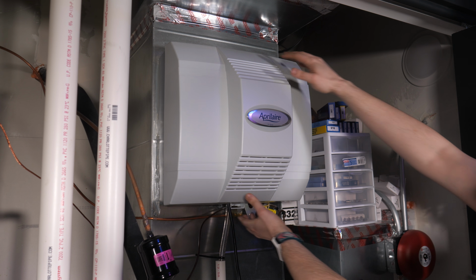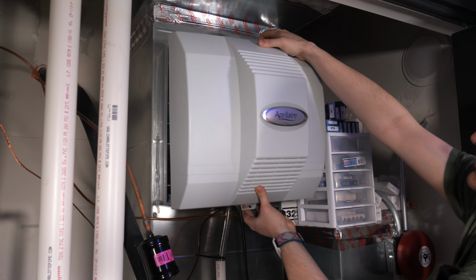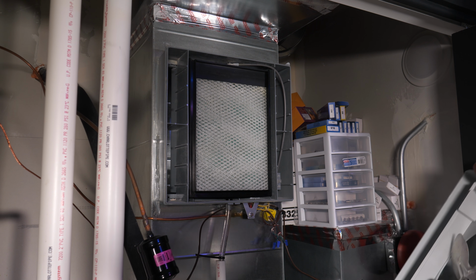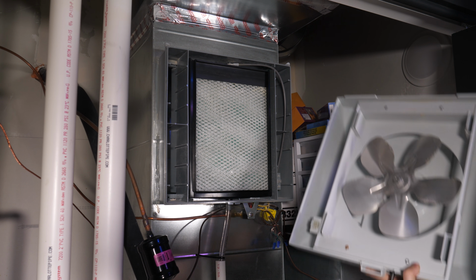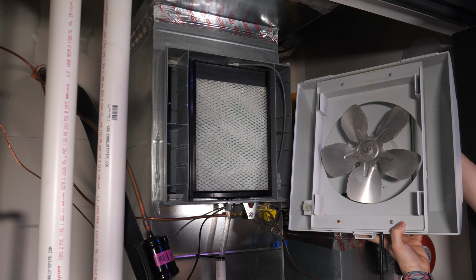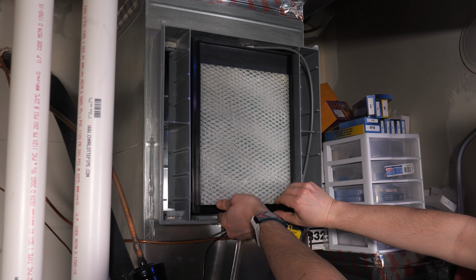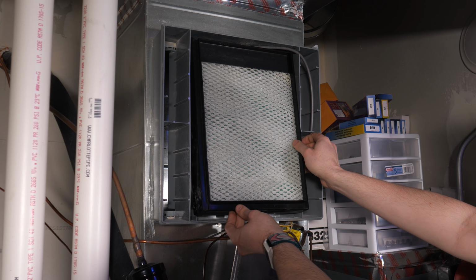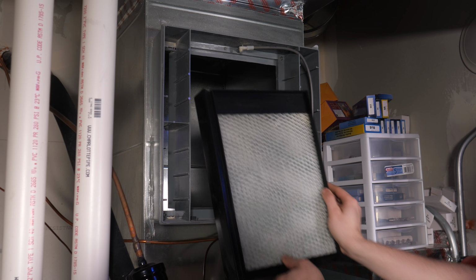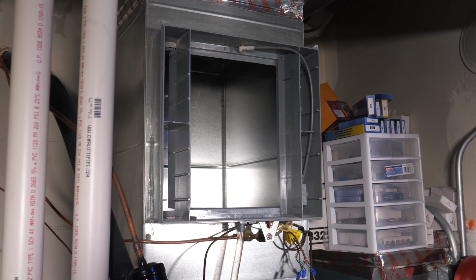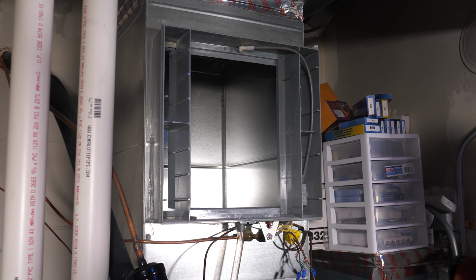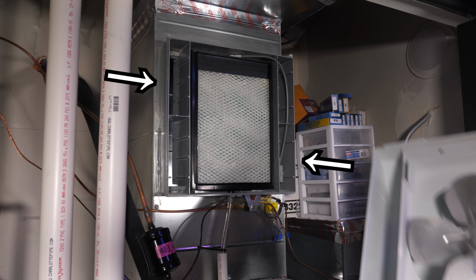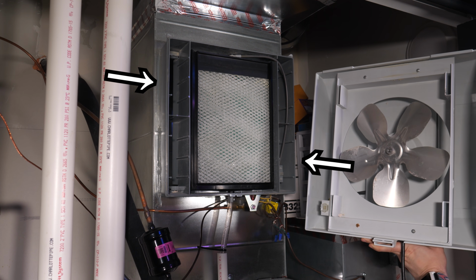There are several types of these things on the market, but most of them are similar to this one. Inside is simply a fan, which blows air through this wet pad made of absorbent material. The whole thing is mounted to a giant hole cut into my HVAC system's ductwork, and when it's running, the fan draws in some of the air coming up from the furnace through the sides here, and then forces it through that wet pad, where it will absorb moisture before rejoining the airstream and getting distributed throughout my home. It's quite a simple device.